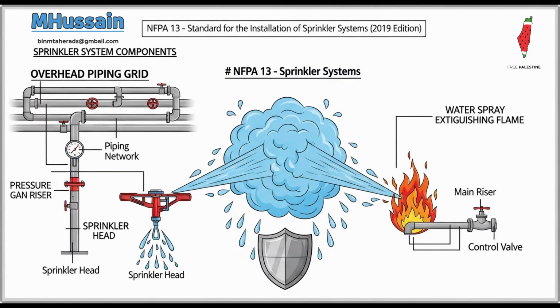And that starts with the jargon decoder. Yeah, let's start with the absolute cornerstone term, AHJ. The authority having jurisdiction. This is often the local fire marshal, could be the building official, maybe an insurance risk inspector. They are the organization, office, or individual legally responsible for enforcing the requirements of a code or standard, or for approving the equipment or the installation. They truly have the final say. If the AHJ doesn't sign off on some deviation or interpretation you made, well, the project is non-compliant. Doesn't matter what the designer believed.